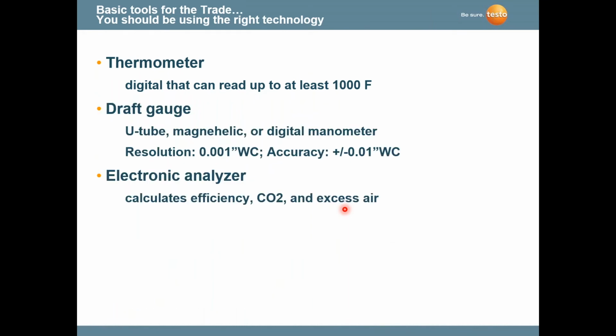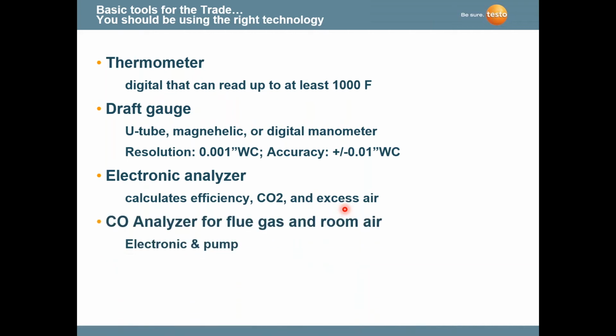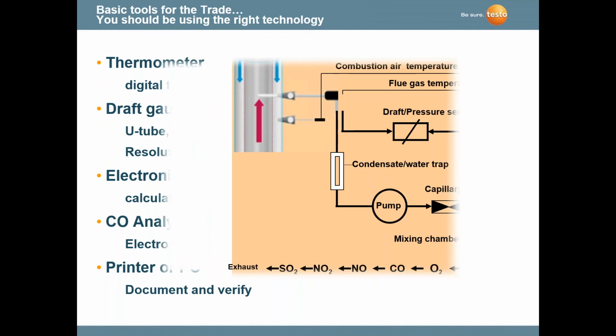And then, we get into some of the instruments and the tools. You'll see that the standard combustion analyzer today has a digital thermometer. We use type K thermometers. We have pressure sensors in these instruments with Testo. A pressure sensor, a draft sensor, is a standard measurement that we do. The instrument has a calculated combustion efficiency. It measures carbon monoxide, both in flue gas and room air. And I believe all of Testo's instruments have the capability of printing, storage capability, and converting to a PC or an app.